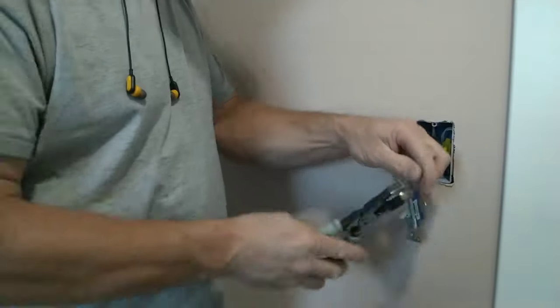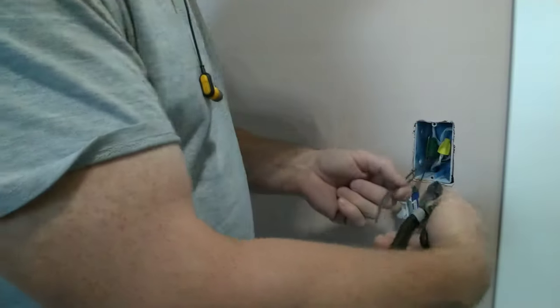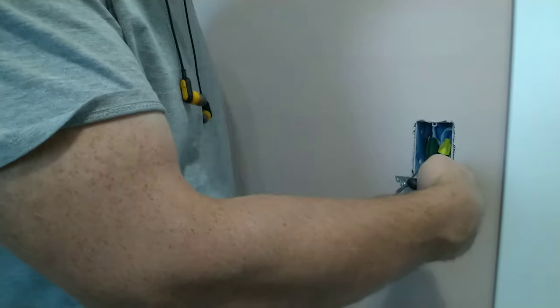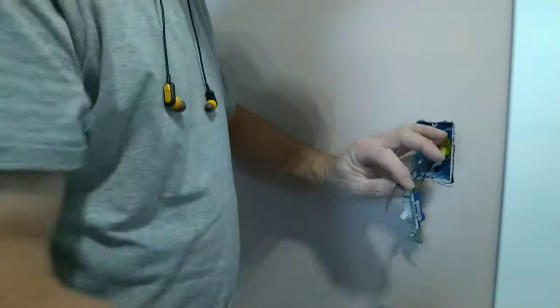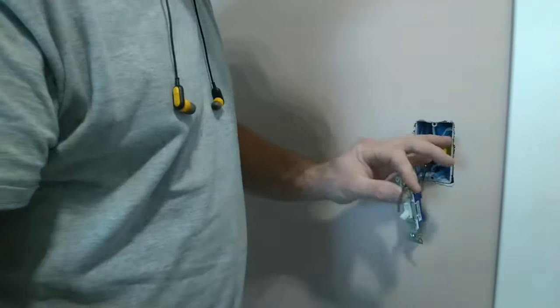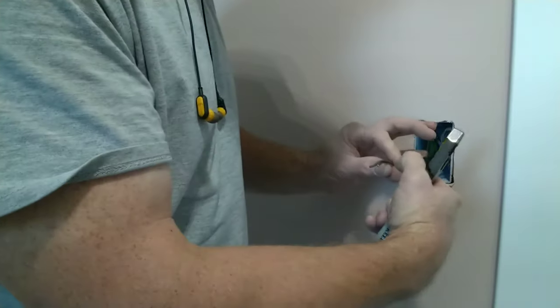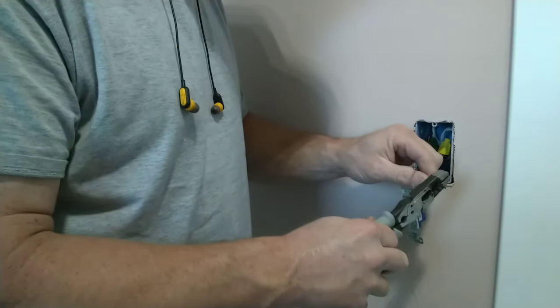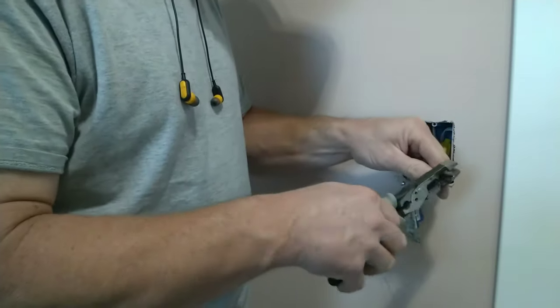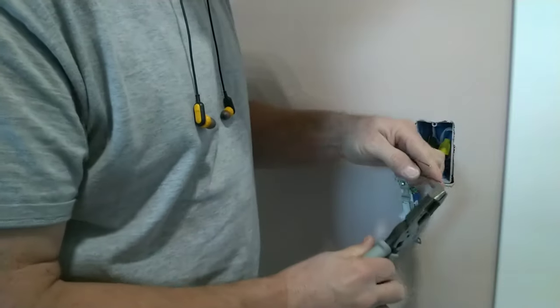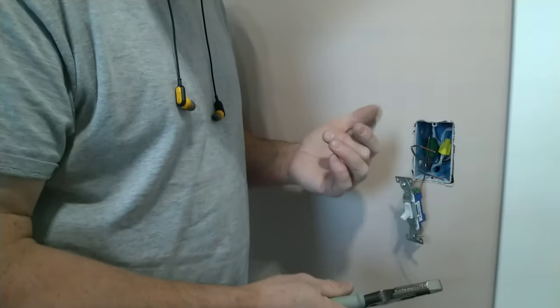Bring your hots out. You want to get an approximate measurement that you're going to consistently use. I never measure, but I've got a good guesstimate of what I want out of the box. But there is a code from the back of the box to the front, a minimum of 6 inches. And when I do them, I always have more than that. The inspector's actually said I'm leaving too much wire. He doesn't mind it, but he said I was leaving a little bit much. I'd rather have a little bit much now so that I can work with it later if there's an issue.